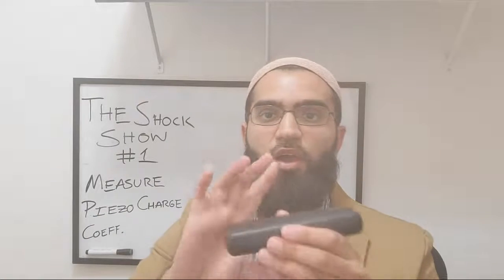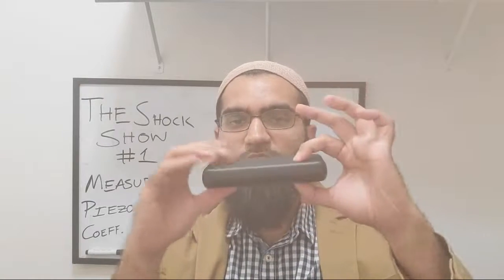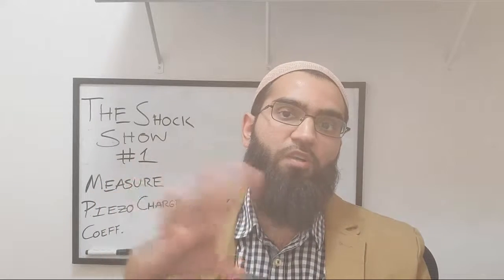What some manufacturers have done in order to avoid frequency dependence is make D33 meters with an alternating force. It'll be like a buzzing, like two mechanical clamps that clamp onto your piezo material, you screw it down, and it applies an alternating force between these two clamps. That allows the cycling to occur, so it avoids that cycling issue. However, there are issues in mechanical clamping. As you're exciting this, there is some movement. There could be some motion based on imperfect clamping, and also the repeatability of mechanical holding interfaces. And also, you're just measuring in one area because you're only applying force in one area.